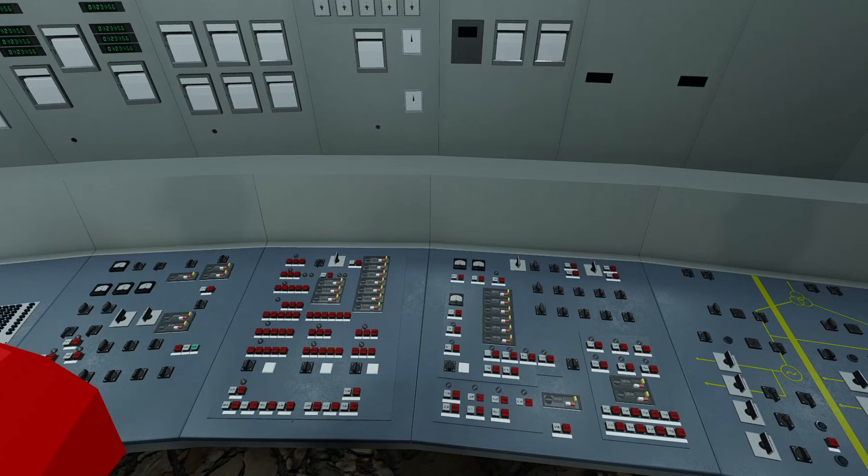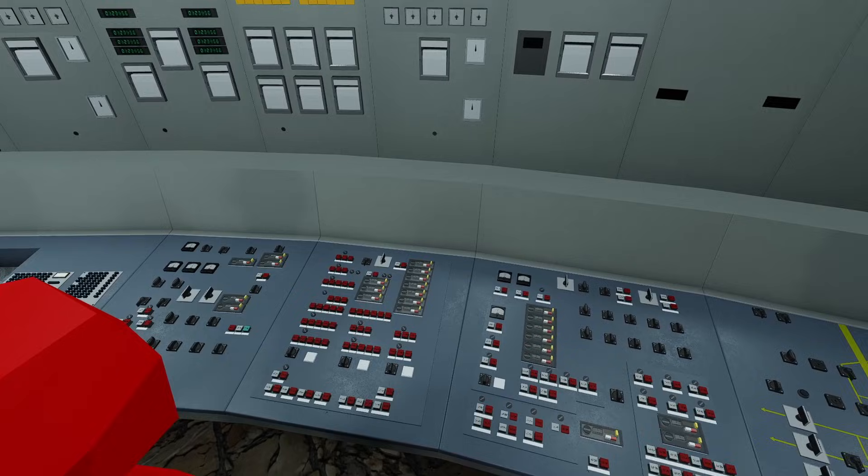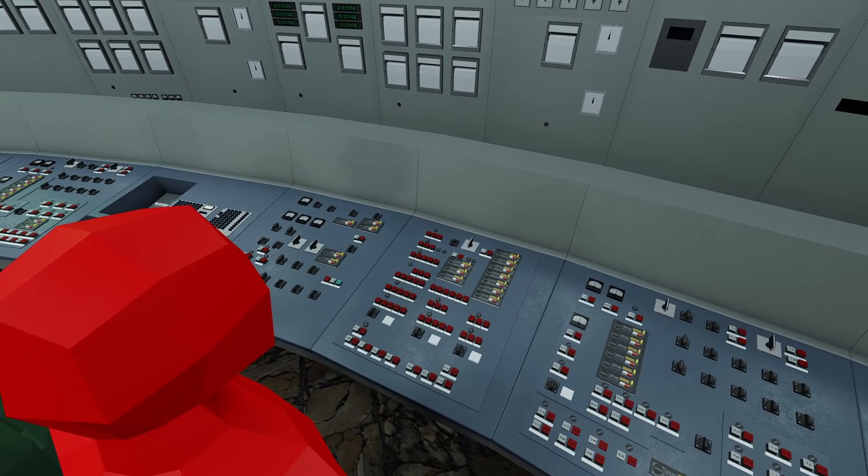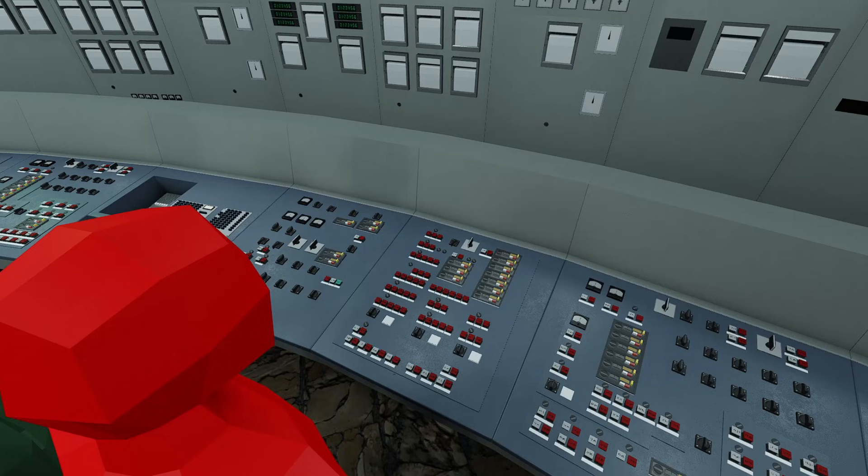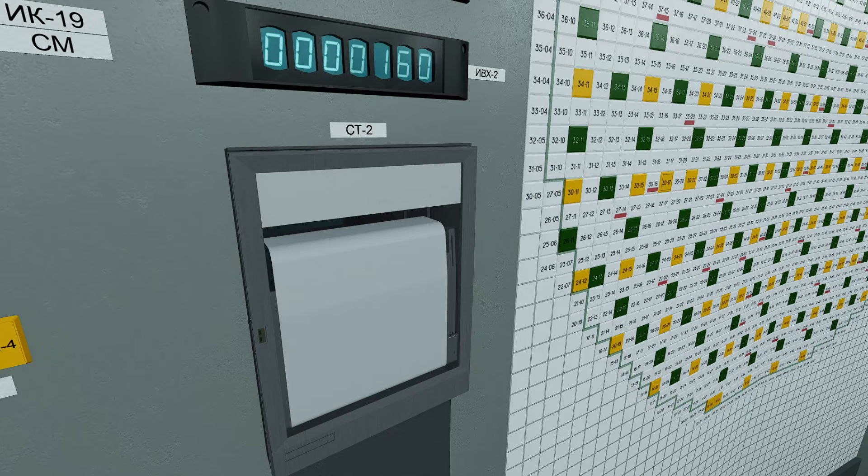Meanwhile, now at 41 minutes past midnight, turbine number eight is disconnected from the reactor at last. Run down to idle for one of the vibration experiments, and would not be reconnected to the reactor for another 35 minutes. Soon after, they managed to reach 160 megawatts, or 5% of reactor thermal output, and switch on the automatic regulators again. Now reactor power was climbing at a comfortable rate again. Too fast at some points, as more water boiled in the core, and the positive void coefficient made itself felt. This would lead to automatic regulators being inserted again, to compensate.